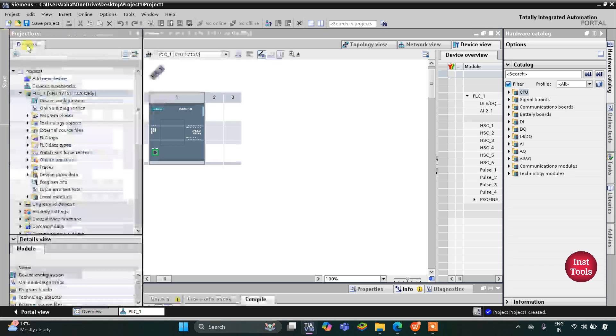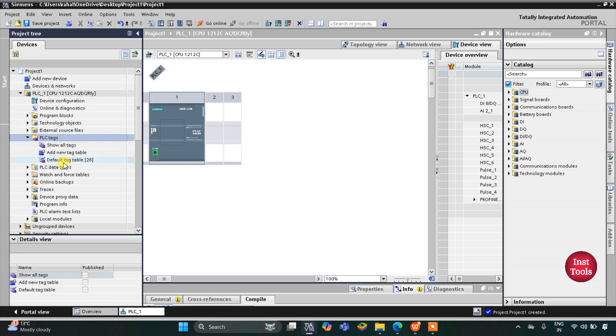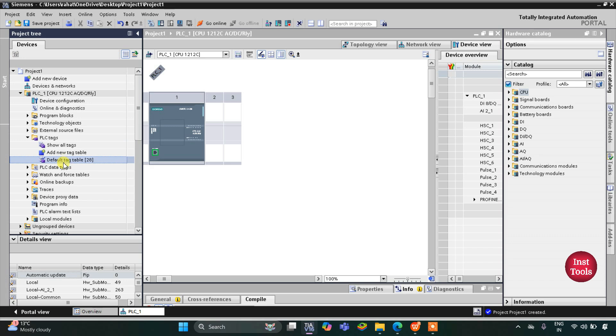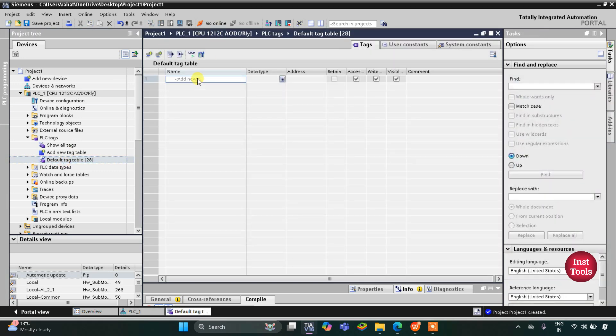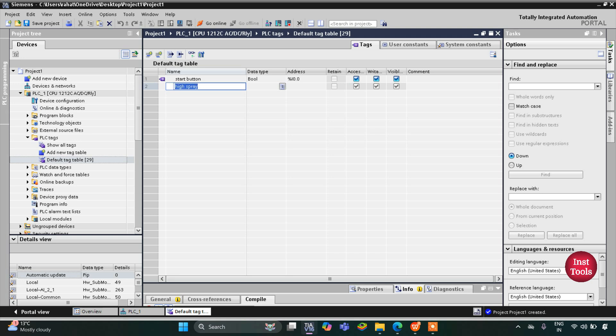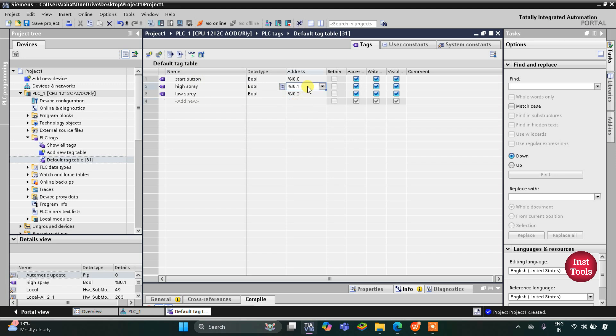First, we need to go to PLC Tags > Default Tag Table. Here we need to add our inputs and outputs. We have one input, that is the start button, and then we have some outputs like high spray and low spray. Since high spray and low spray are outputs, their addresses will start with Q — Q0.1 for high spray and Q0.2 for low spray.